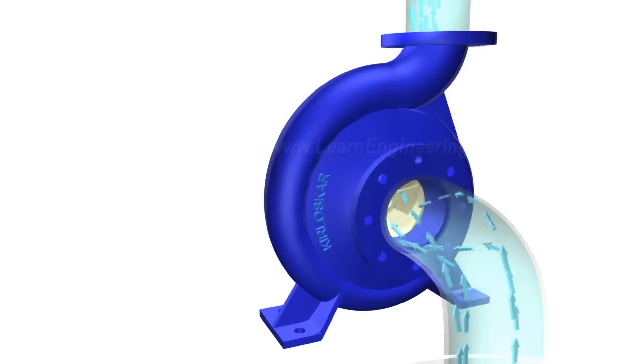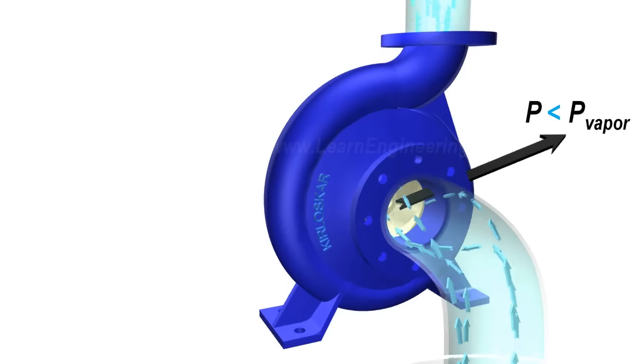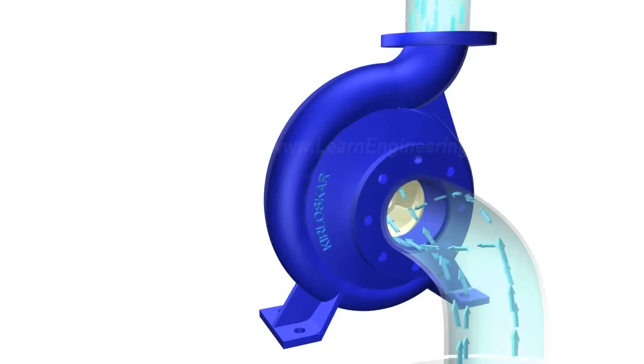If pressure at the suction side of the impeller goes below vapor pressure of water, a dangerous phenomenon could happen. Water will start to boil, forming vapor bubbles and spoil impeller materials over time. This phenomenon is known as cavitation.